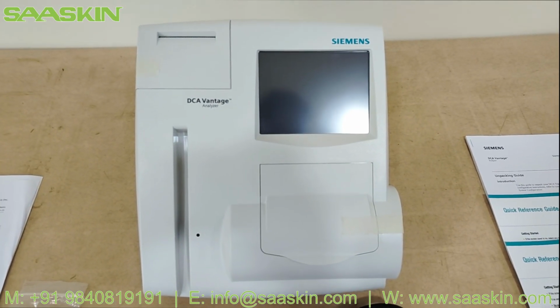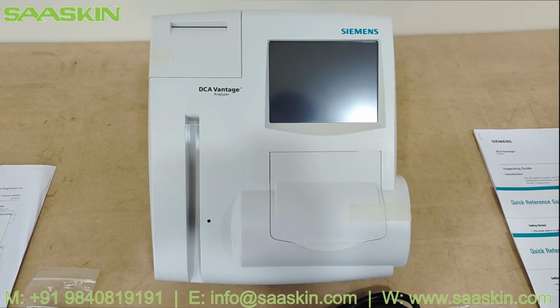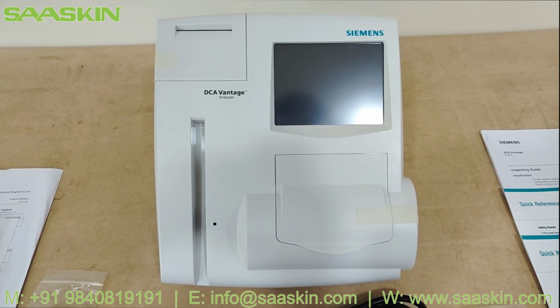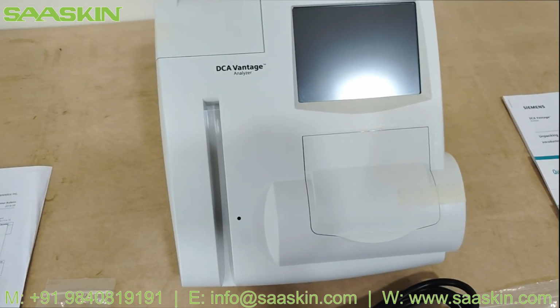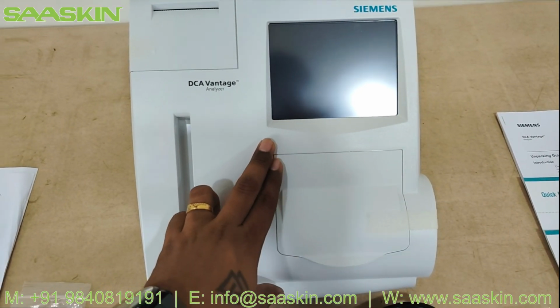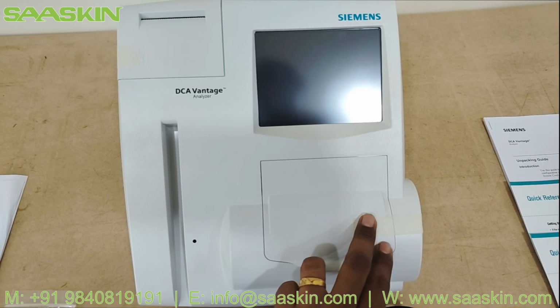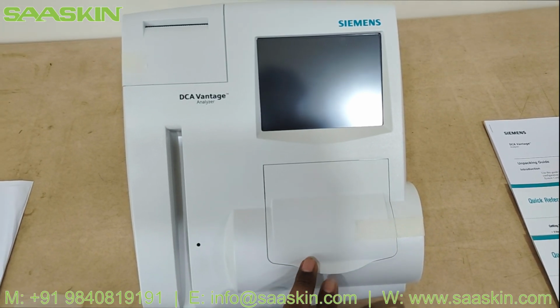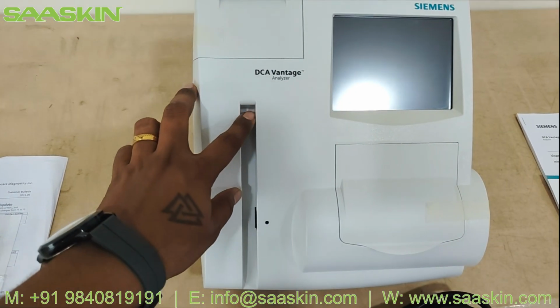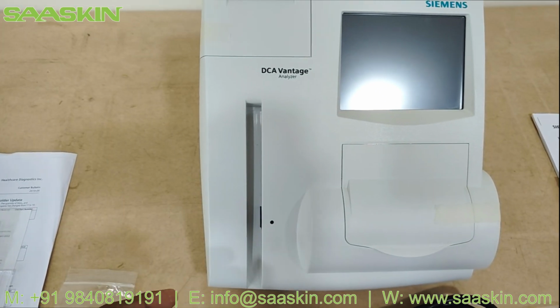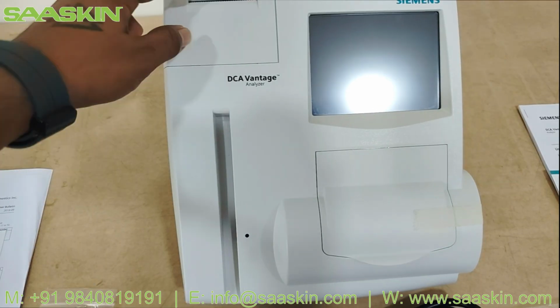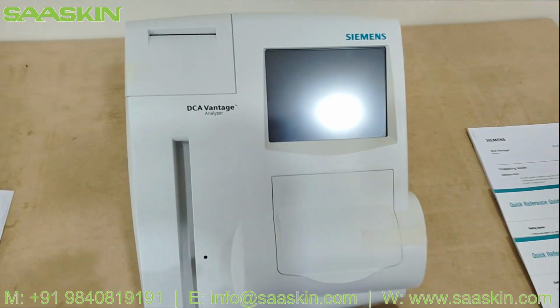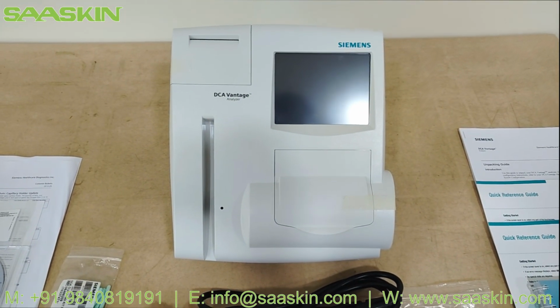This is the Siemens DCA Vantage Analyzer used for microalbumin and HbA1c test, and you can find the display over here. And here is the part you can insert the cassette with sample, and here is the place you will scan the calibration card and cassette, and you will get the printout of the result over here. And this is the front view of the analyzer.